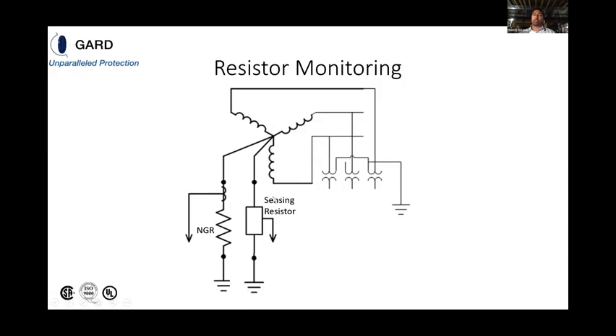Many of the products out in the market right now use a DC-based injection method, and when that DC-based injection reaches this XO point, it sees these inductances as short circuits. So if you have YY connected PTs in your setup, the DC-based injection that the competitor is using may find an alternative path, in which case it may falsely presume that the NGR is still in the system. So that's the way that we've mitigated that with our high frequency AC injection.